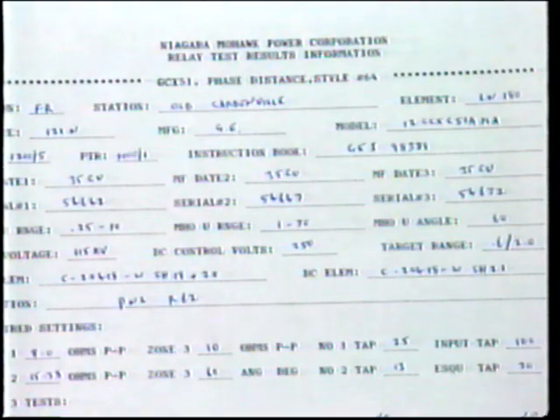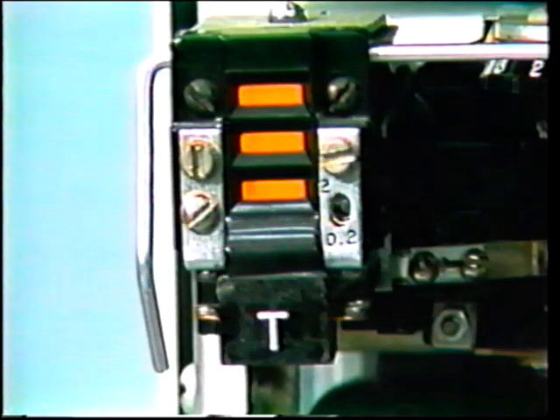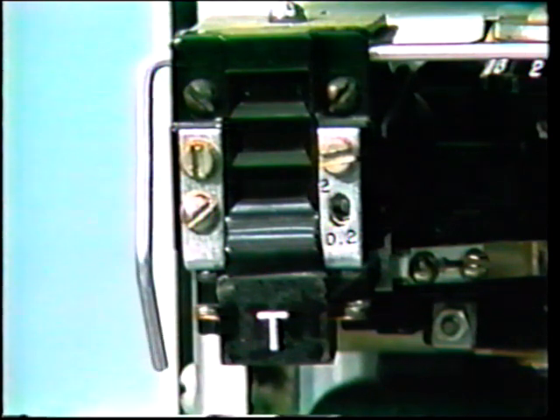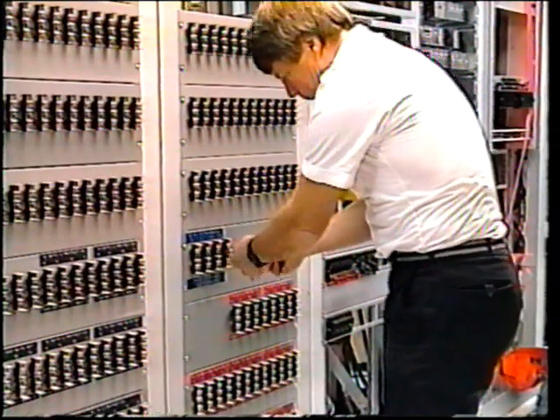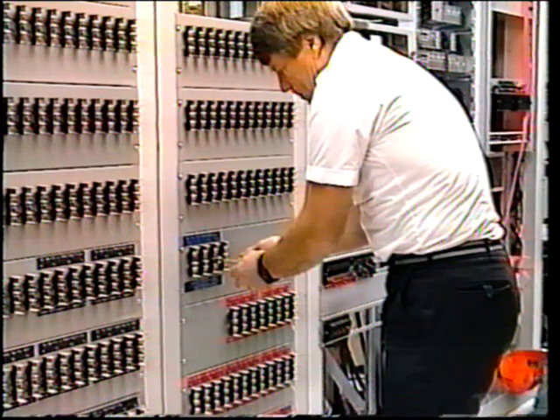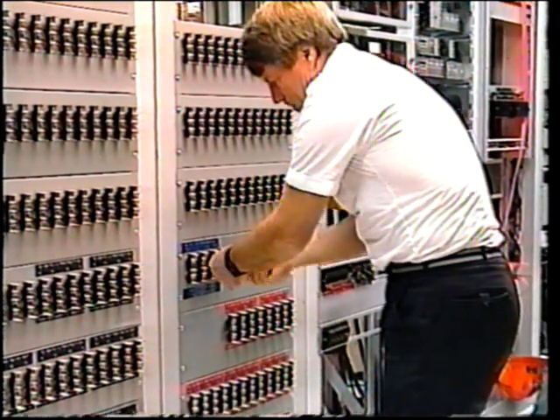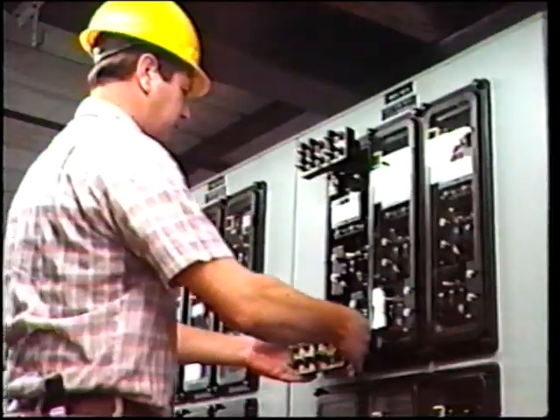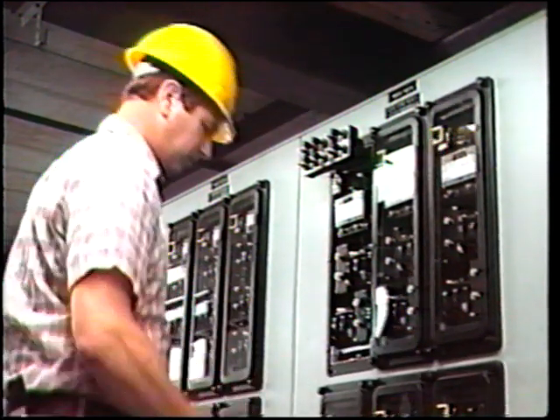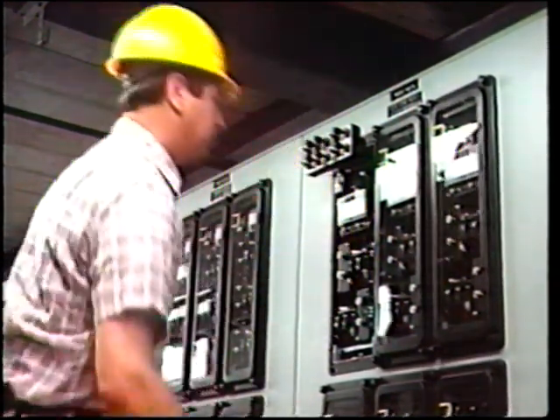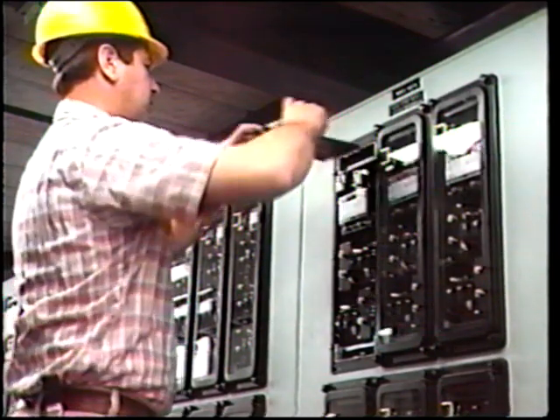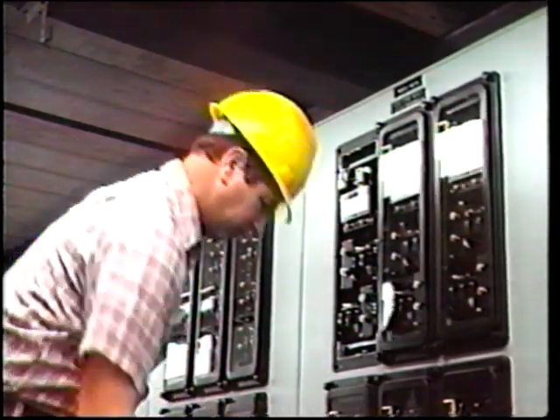All of the results from calibration and operational testing of the various protection devices must be clearly marked on the test record sheets. At the completion of the tests, all relay targets, annunciators, and alarms should be reset. Also, all test switches, sliding links, and so on must be returned to the appropriate position. Similarly, remove all test fixtures, leads, plugs, jacks, etc., and restore the equipment to its normal operational condition.